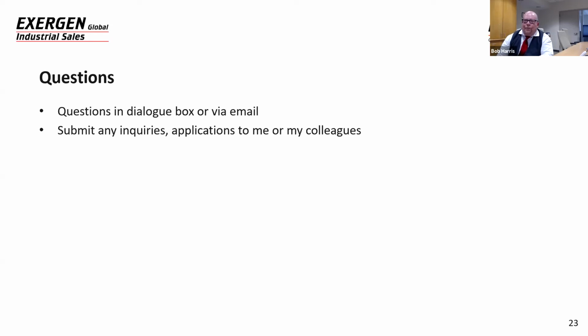And for these applications, and even some like Brian mentioned that are non-medical, we've come across some in the food and beverage industries where they're boiling water and the sensor's at room temperature. Something like that is much easier to do because you have more signal to work with. So the bigger the delta T, the better. We can work with very small delta Ts, but it could be a difficult calibration. The other thing to look out for is a low emissivity surface. Combined with a low delta T, that may also give you some challenges because you really don't have a lot of signal to work with. So the bigger the better.